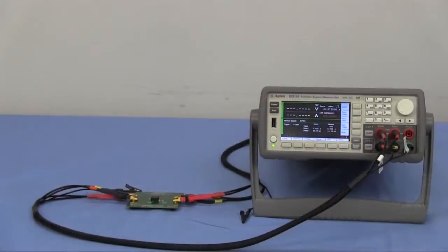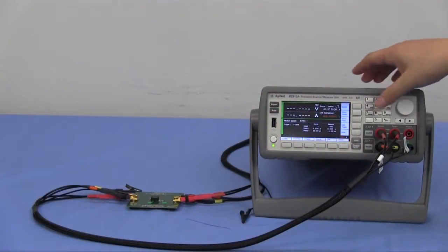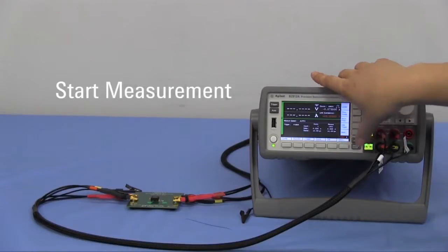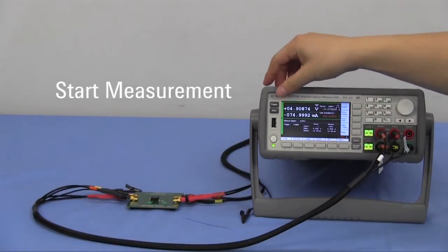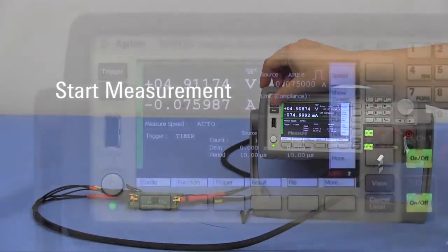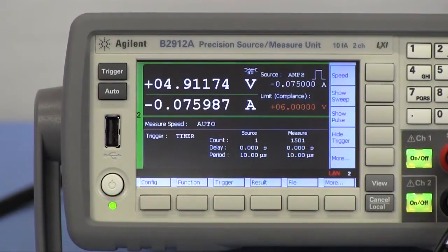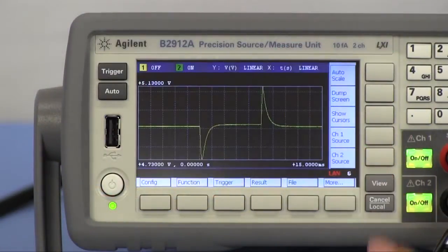After setting up the channels, press on-off button for both channels to enable the outputs, and then press trigger button to start measurements. The measurement result can be seen graphically in graph view on the instrument.